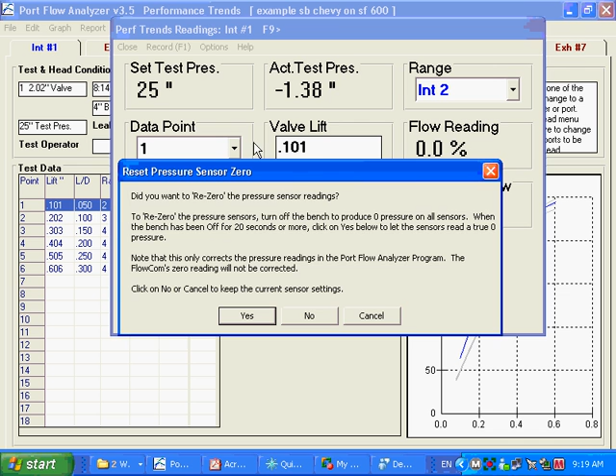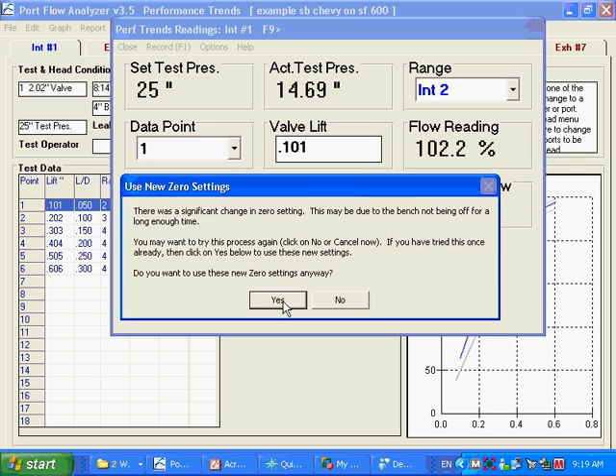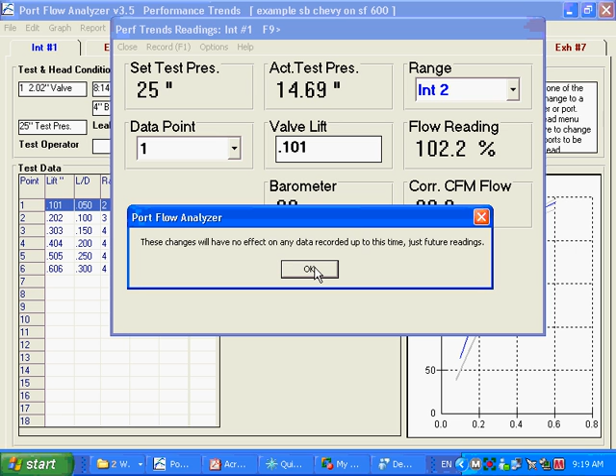Now you're saying with the bench not running, why is it reading anything? Well, that's because like most systems, you have to re-zero them. They drift off a little bit, and that was a factory calibration. So we have this command under options to re-zero the pressure readings, and I say yep, I want to re-zero them. It says there was a significant change, and asks do you want to keep them? And I say yes. It's telling me that this will not back calculate anything we've done previous to this - it only affects data coming up. So I say, yep, I know that.